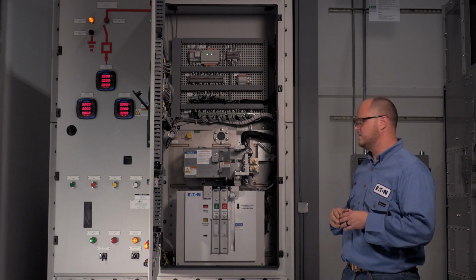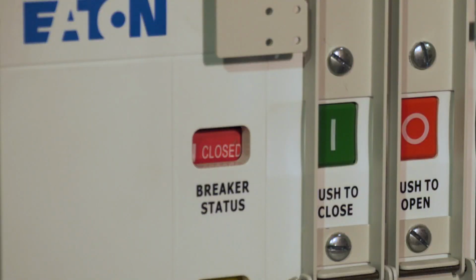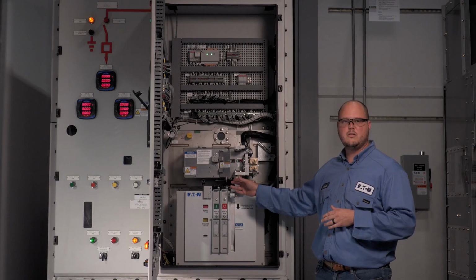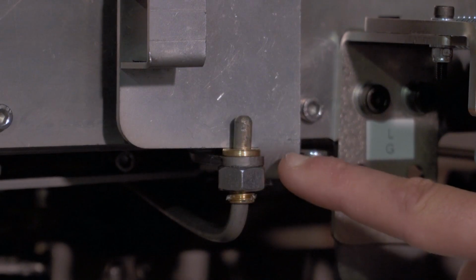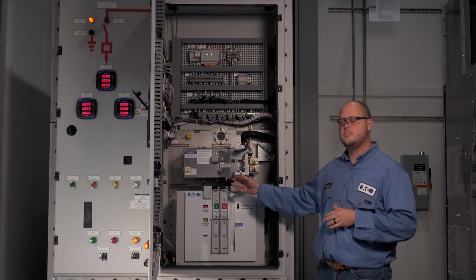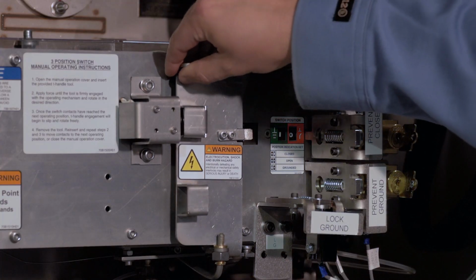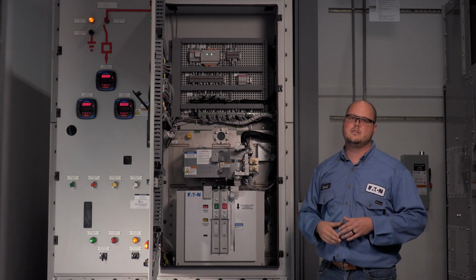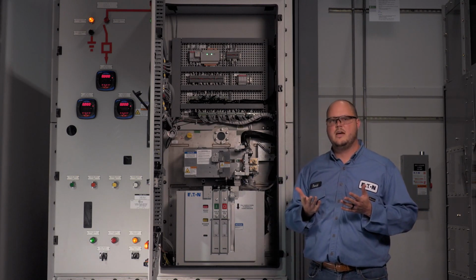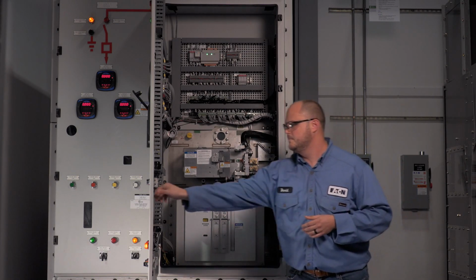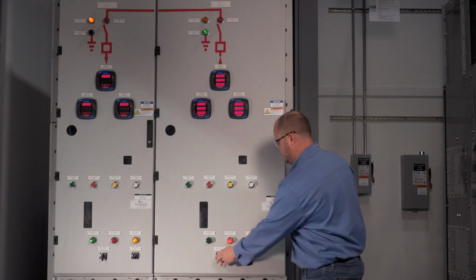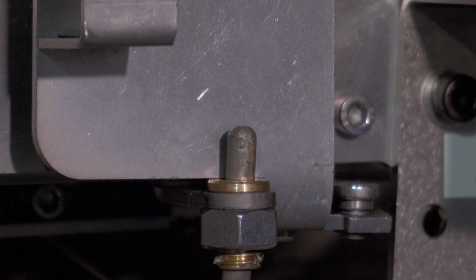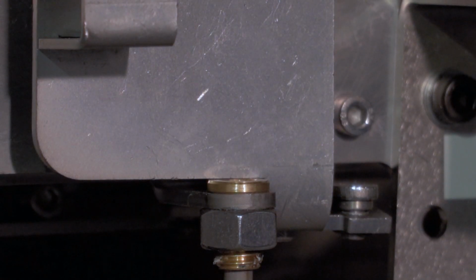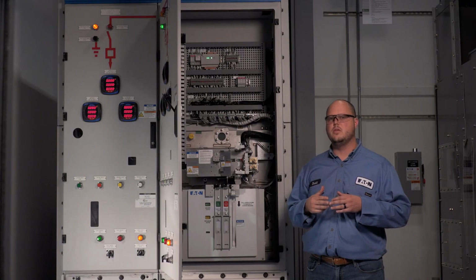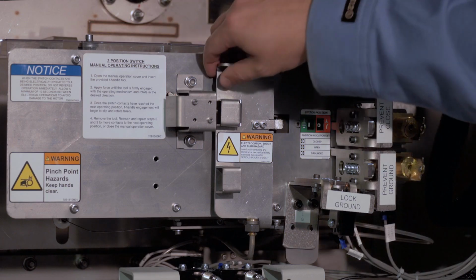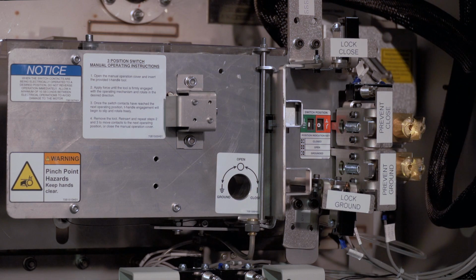Here you can see the circuit breaker is closed, and you'll notice that the interlock plunger is engaged and blocks access to the 3-position switch operator cover. This prevents manual operation of the 3-position switch.